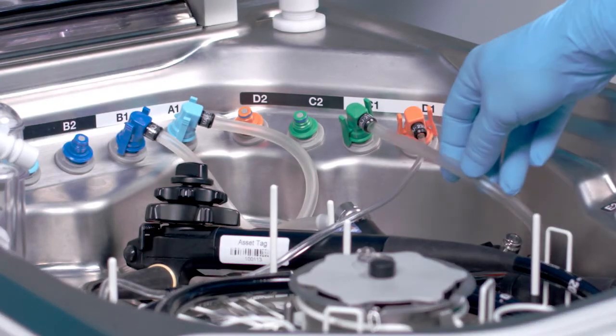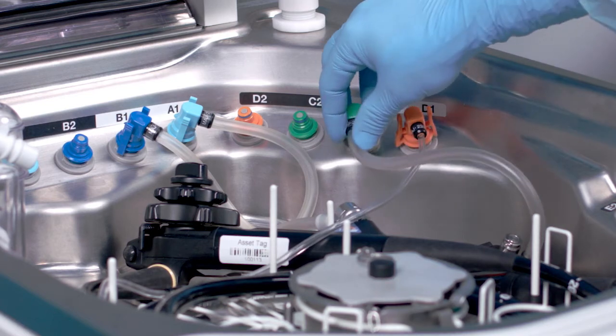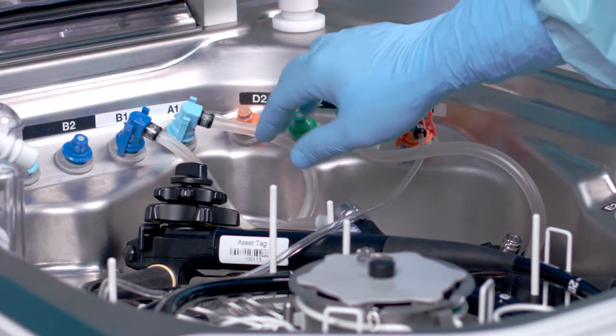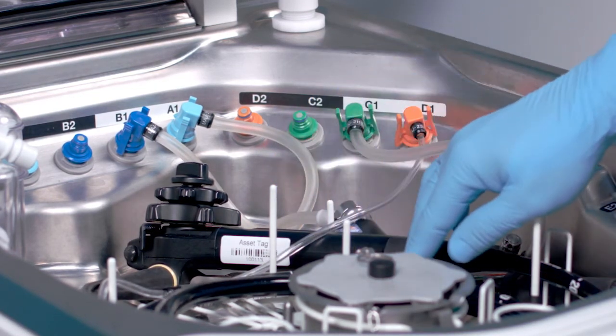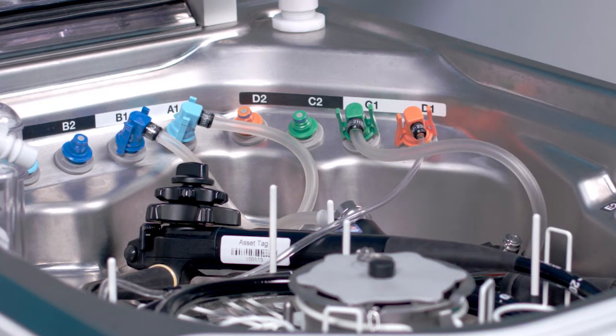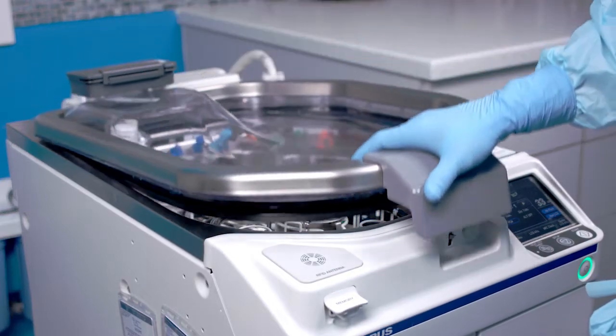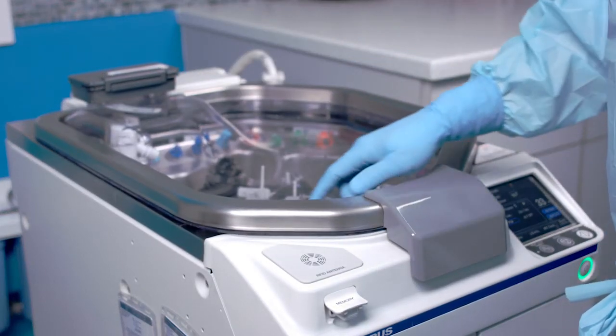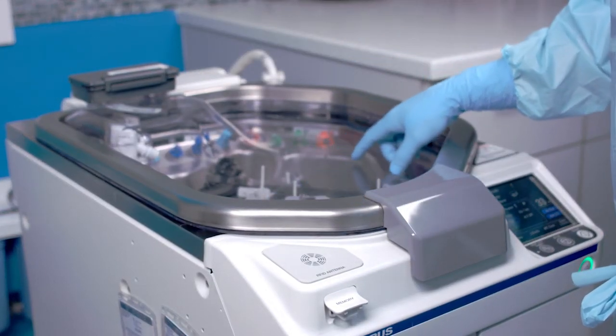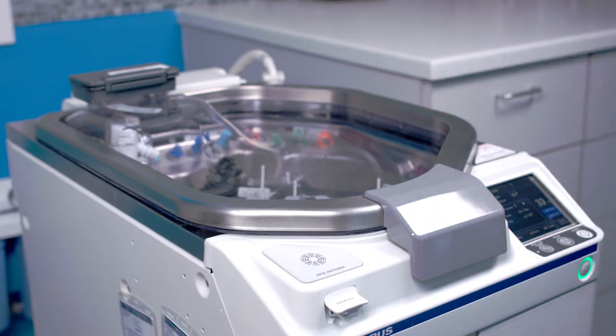Inspect all the connecting tubes for kinks or irregularities. If any exist, reposition the connecting tube to remove kinks or irregularities which may cause improper reprocessing. Now, all that's left is to simply close the lid and check to ensure that the lid is not touching any portion of the endoscope. Press the Start button to begin the process.